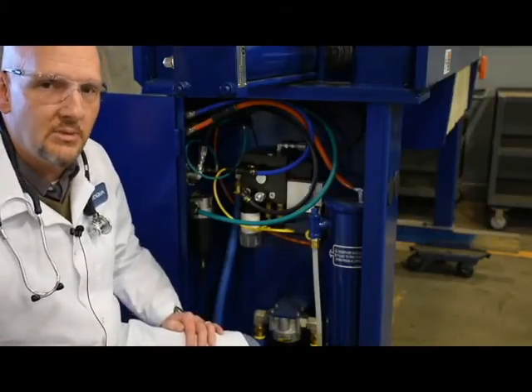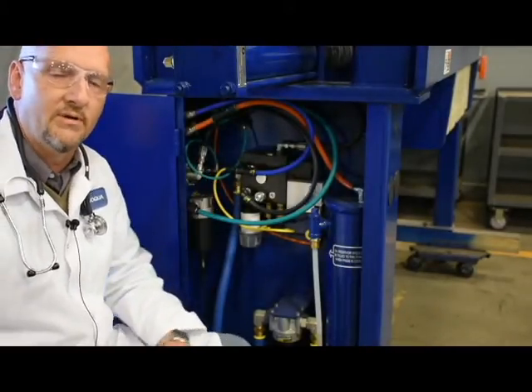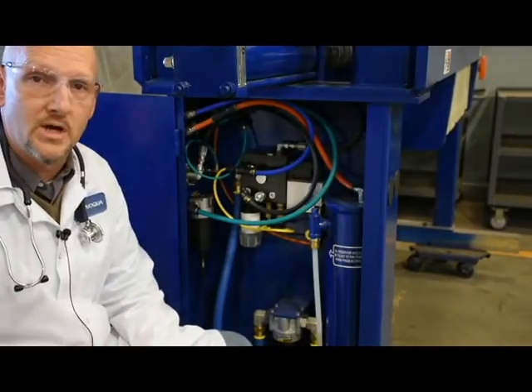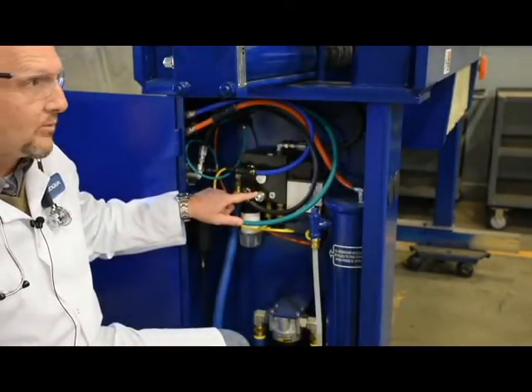In a lot of cases, the first place I would look is a relief valve. Now every system has a relief valve and it's there because we don't want to over pressurize the machine. In this system, the relief valve is located right here.